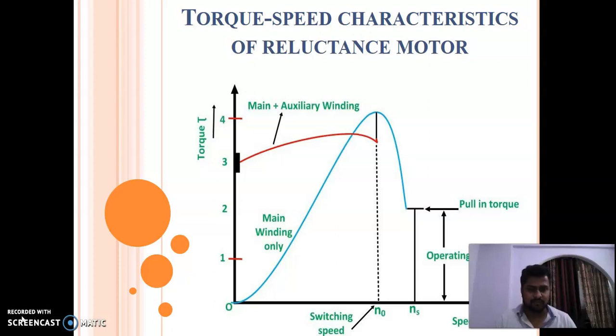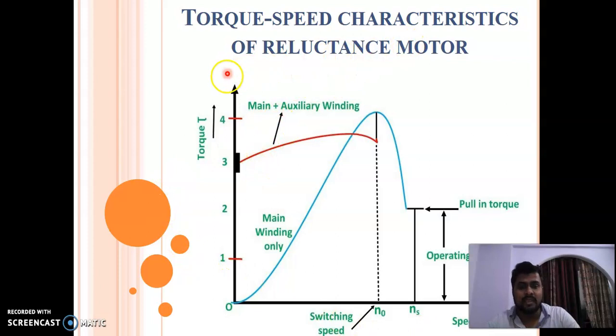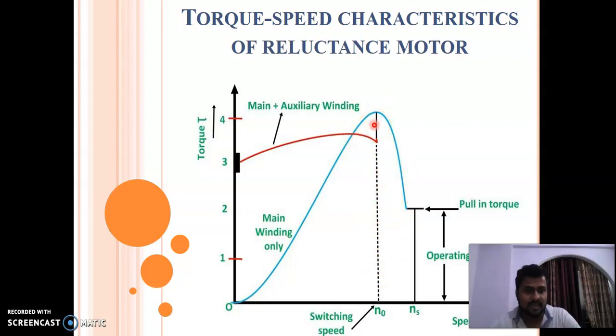Now let us take the speed-torque characteristics of the reluctance motor. On the y-axis we have torque and on the x-axis we have speed. At zero speed the slip will be unity, and at speed equal to synchronous speed the slip is zero. At the time of starting, both main and auxiliary windings are energized and the characteristics follow a certain curve. At approximately 70 to 80 percent of synchronous speed, the centrifugal switch opens and only the main winding remains, shown by its own characteristic curve.